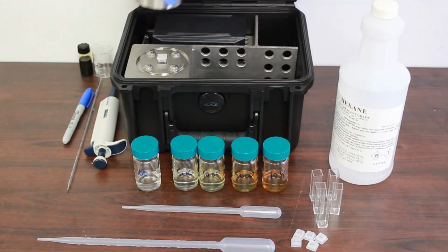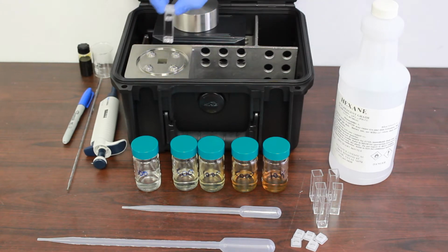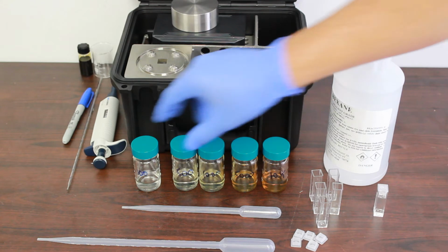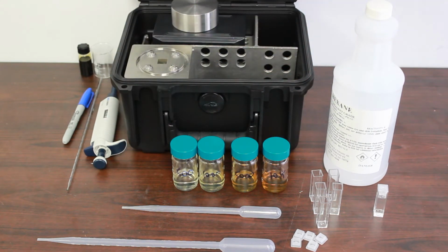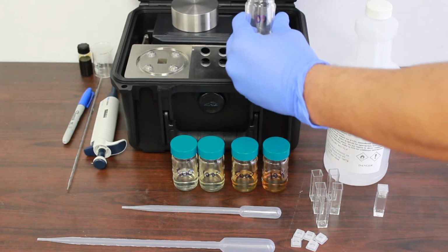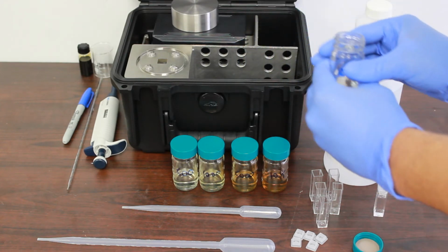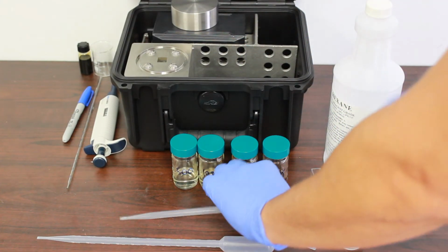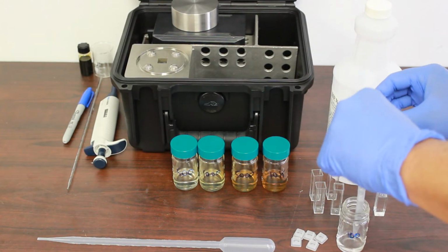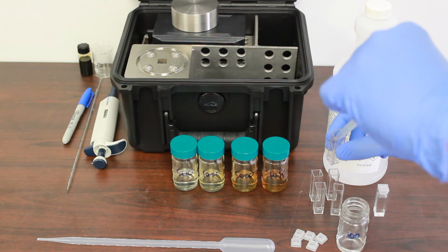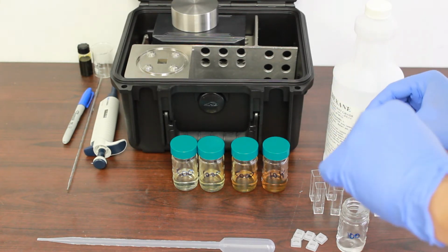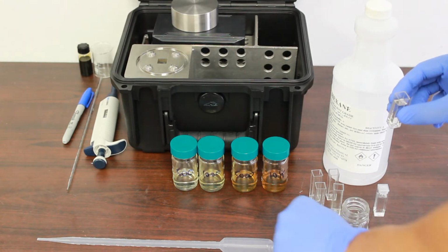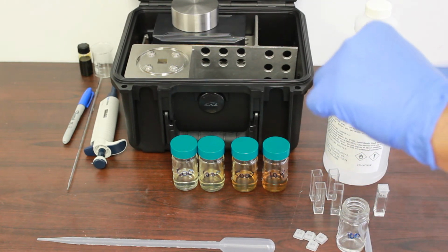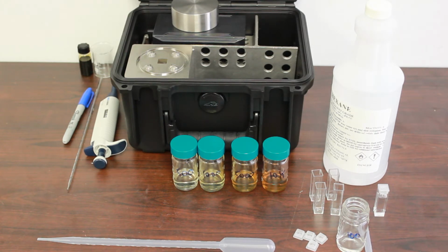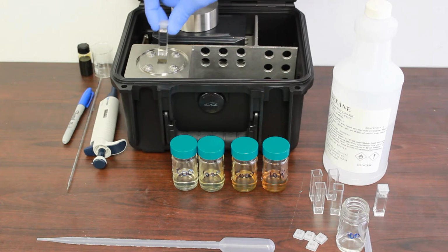The next standard to be calibrated is 100 ppm. First, remove the 0 ppm standard from the cuvette cell. Select the 100 ppm standard and shake it for at least 5 seconds. Using the 5 ml disposable pipette, insert some of the 100 ppm standard into a cuvette. Put the cap on the cuvette and wipe the cuvette outside as needed before inserting it into the cuvette cell of OWB.